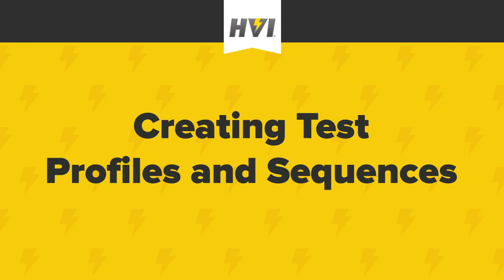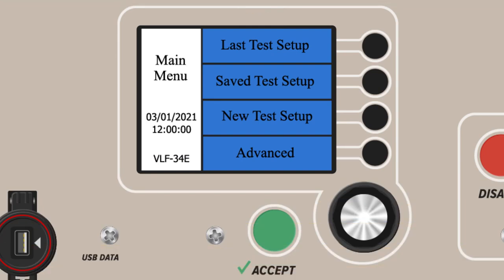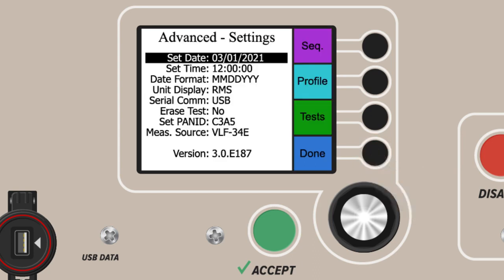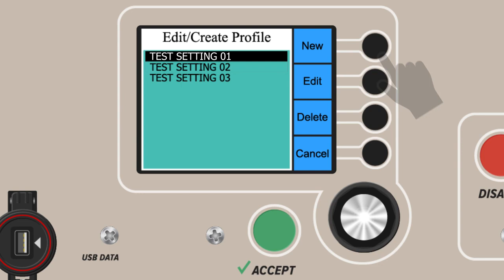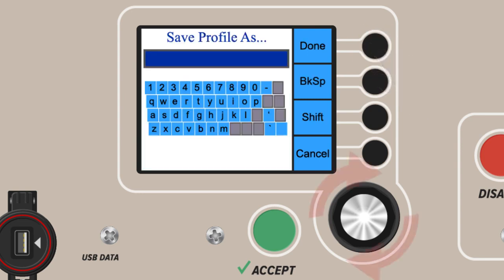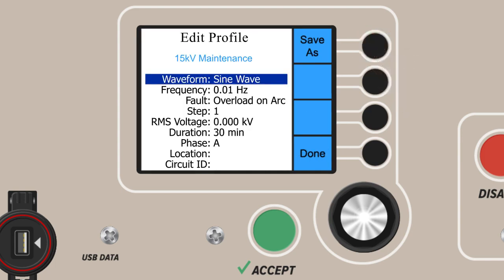Creating test profiles and sequences. In this section, we'll show you how to create test profiles and sequences. As a hypothetical example, we'll create and name a test for the maintenance of a 15 kV cable, according to the IEEE 400.2 2013 standard. With your device on, first, press Advanced. Select Profile. Select New. Save the name and press Done when the name is correctly entered.